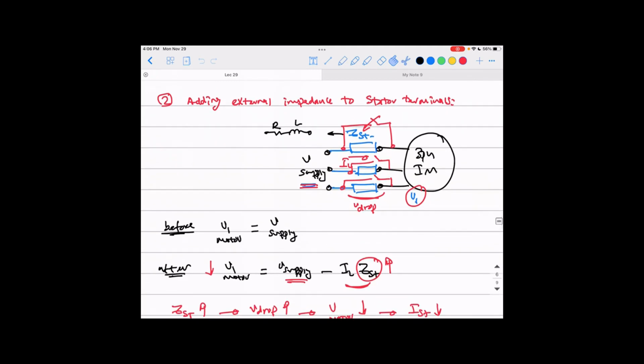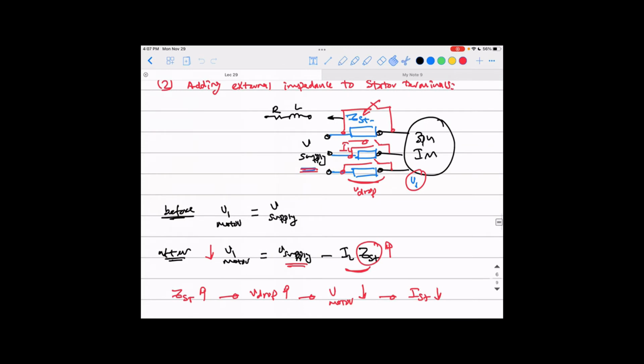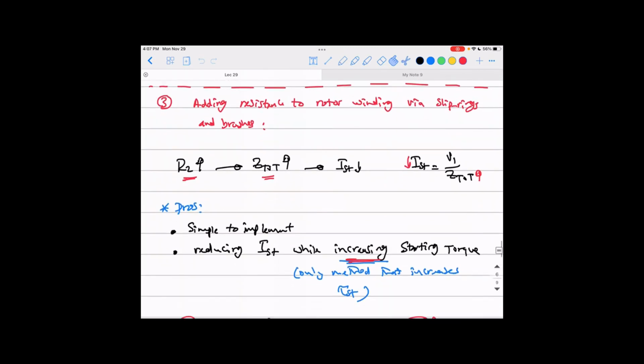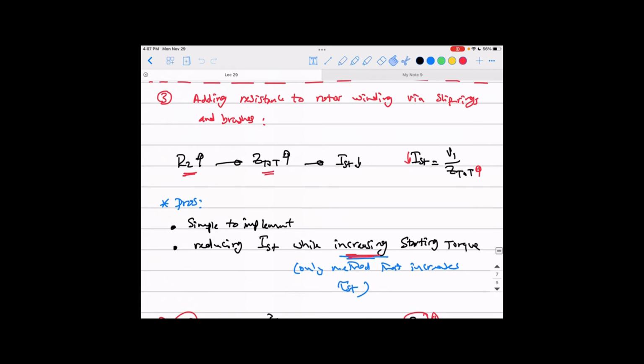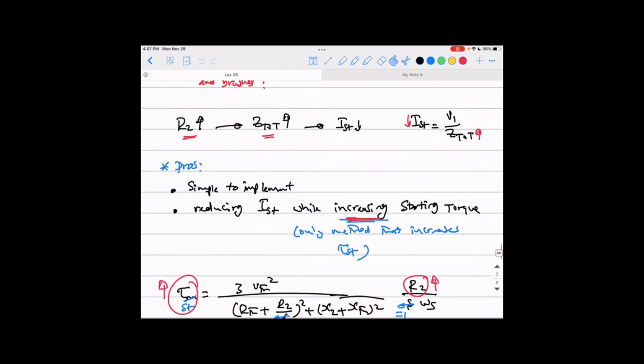The second one we just talked about is adding an impedance to the stator terminals for the starting period, and then adding a switch in parallel with it and switching it on after the starting period passes, which bypasses this resistance or impedance and gets the motor directly connected to the supply voltage. This impedance takes some voltage drop, which is subtracted from the supply voltage, so the motor voltage is a little bit reduced, and this reduces your starting current. The third method is doing the same, but adding resistance to the rotor winding if you're talking about a wound rotor machine, via the slip rings and brushes. And like we said, it basically increases the total impedance of the machine, and thus reduces your current.